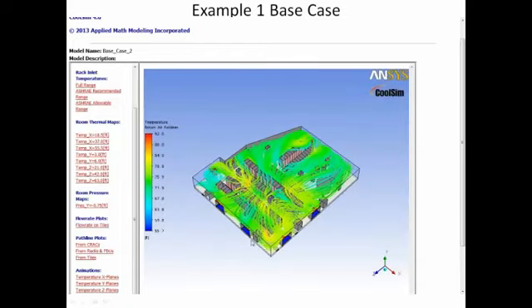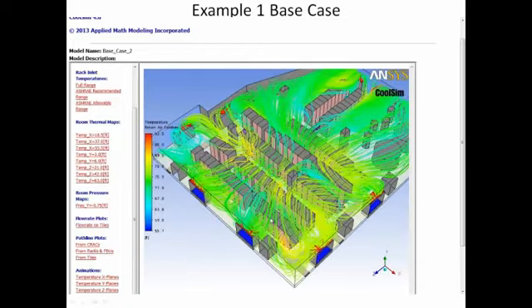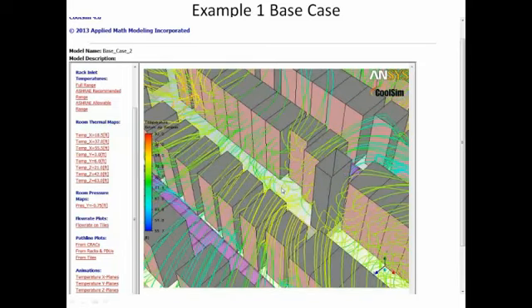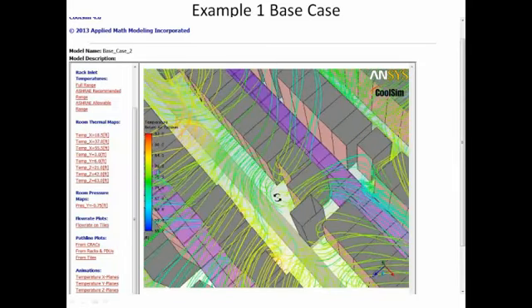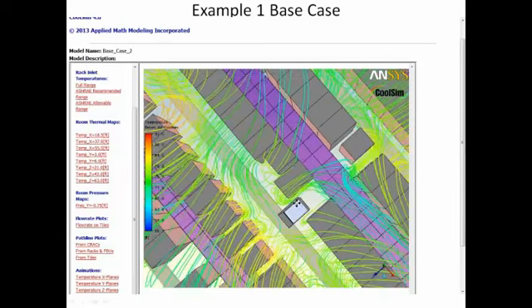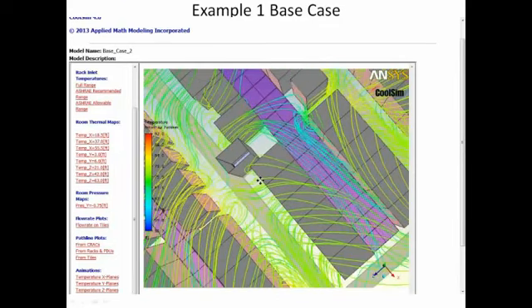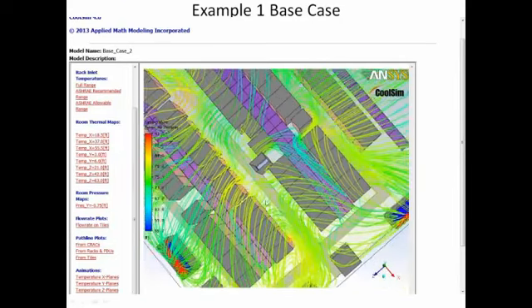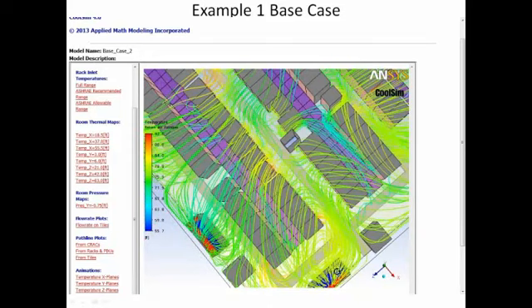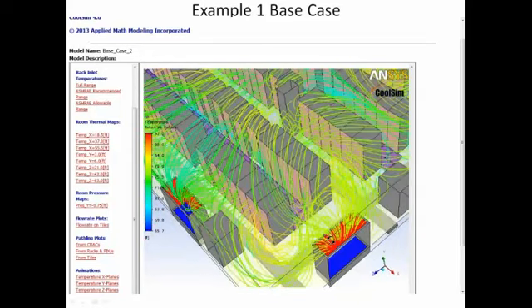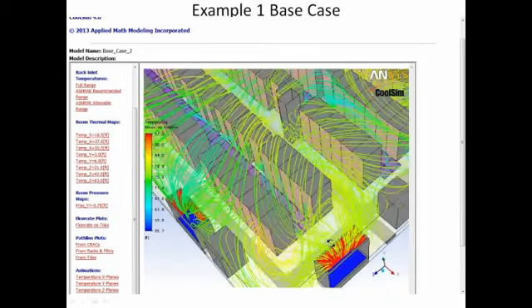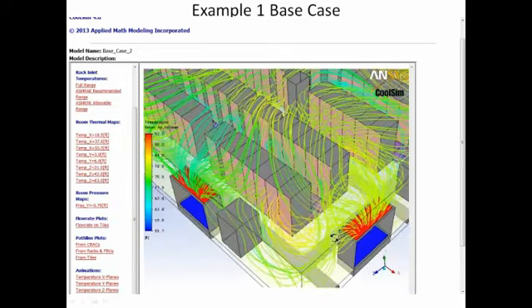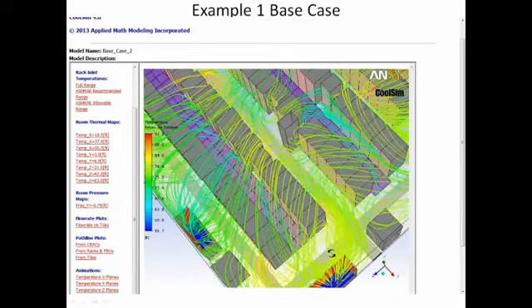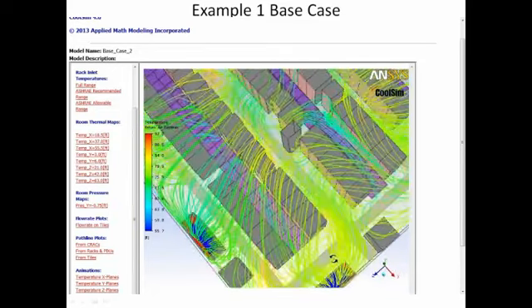This one is pathline plots from the racks, and what I'm doing here is showing you only the air coming out of the rack itself and going supposedly back to the cooling unit. But you see what happens here in this design, Magnus, we've got a cooling unit over here and a cooling unit over here. So the air is going to come up, and it wants to get back to those cooling units. But on its way, it gets sucked into the intakes of some of the other units. I'll show you two spots where recirculation is occurring.